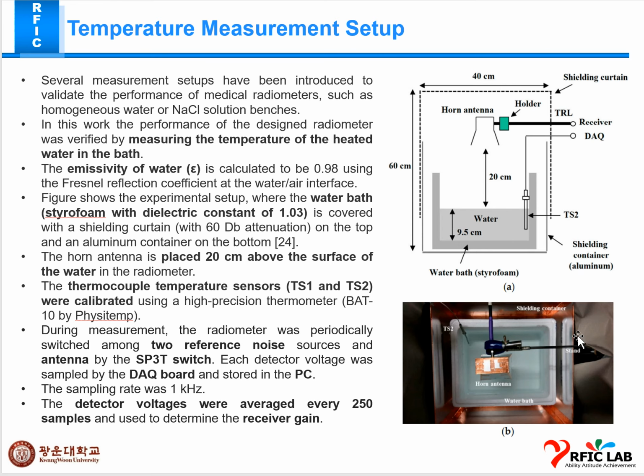First of all, several measurement setups have been introduced to validate the performance of the medical radiometer. In such, a homogeneous water NaCl solution is used, and by measuring the temperature of heated water in a bath, the emissivity of water is calculated to be 0.98 using the Fresnel reflection coefficient at the water-air interface.